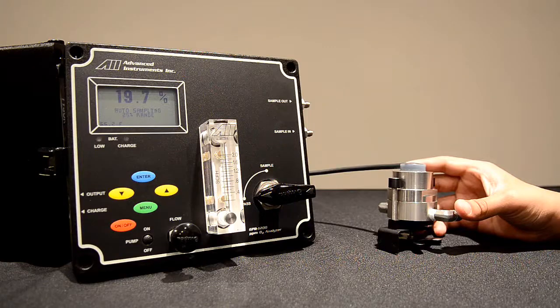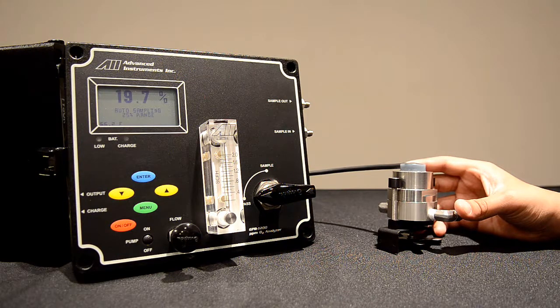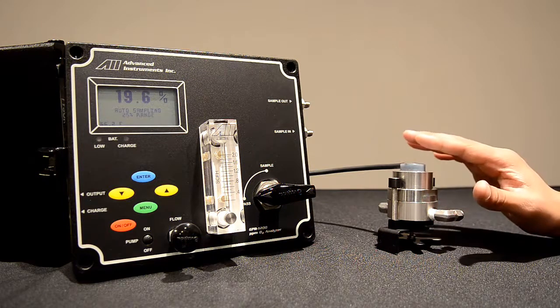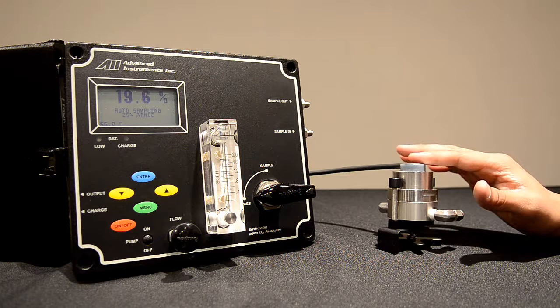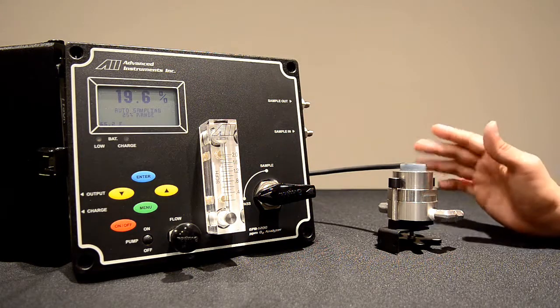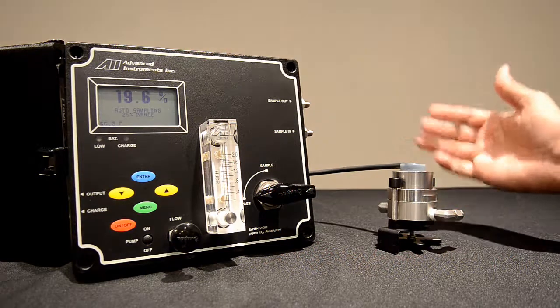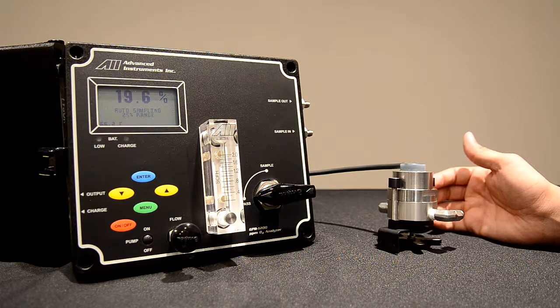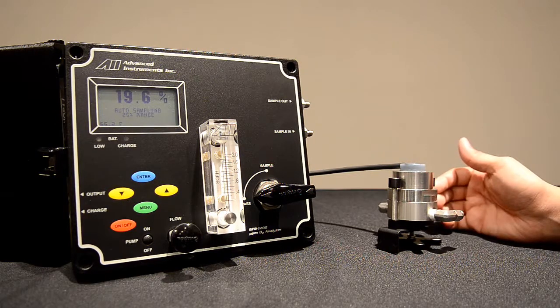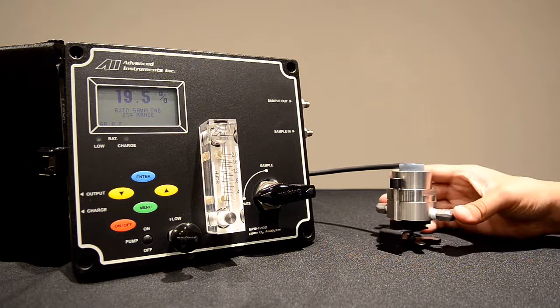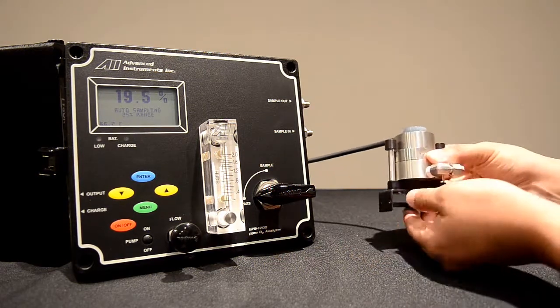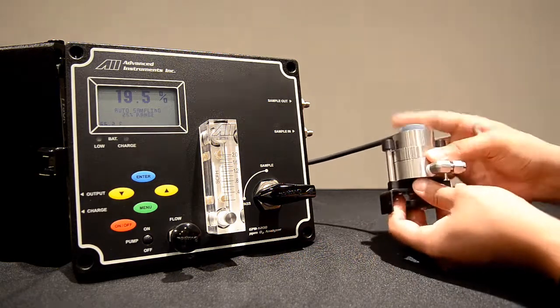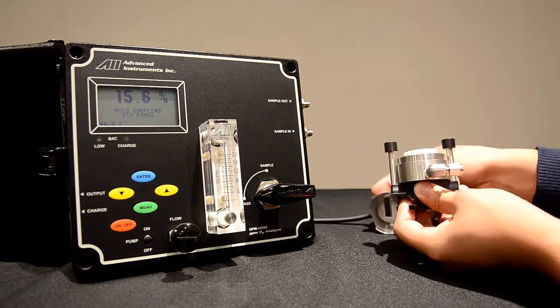We will now perform an air calibration on the GPR 1200. When you receive the GPR 1200, the oxygen sensor will come installed inside the analyzer, inside the sensor housing. For demonstration purposes we have removed the sensor housing from the interior of the analyzer. However, when you have the unit, this housing will be plumbed inside the analyzer. To remove the sensor and expose it to air, we loosen the fittings at the bottom of the sensor housing, rotate the top sensor housing and slide off.